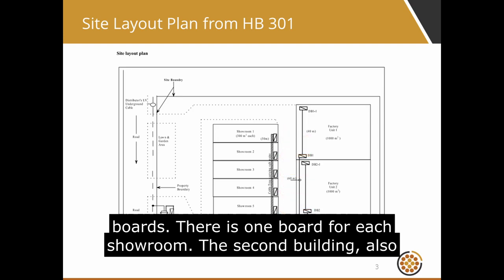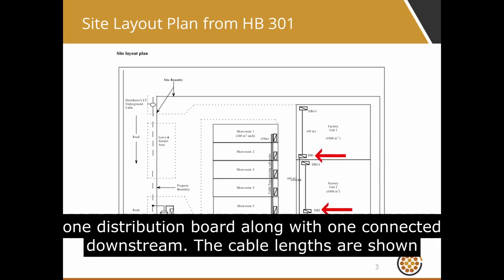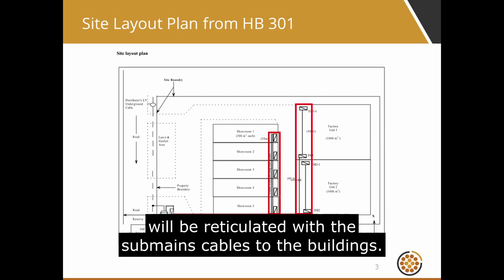The second building, also connected to the metering panel, contains two factory units. Each factory unit has one distribution board, along with one connected downstream. The cable lengths are shown in the diagram, which will be important later for cable sizing. A protective earth cable will be reticulated with the sub-mains cables to the buildings.